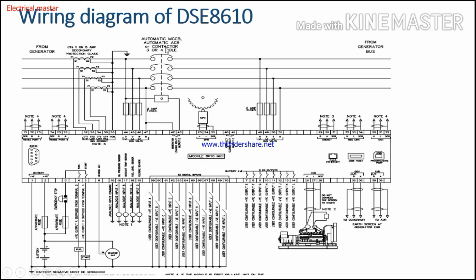And see, this is the outgoing breaker I mentioned, an automatic MCB. You can use an MCCB or ACB, whatever it is, or a contactor is also acceptable. That breaker's control supply, the phase supply, is given directly from the generator output. Only the neutral will be taken to the NO of the Deep Sea controller. So whenever the Deep Sea controller senses that voltage and current are okay, the NO becomes closed, then the magnetic contactor will energize and allow the power to flow from the generator output side.